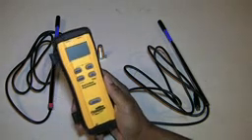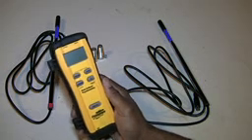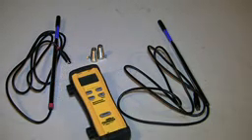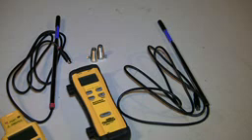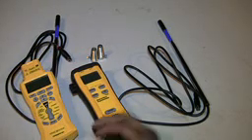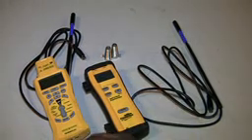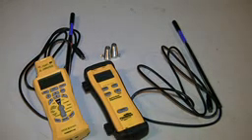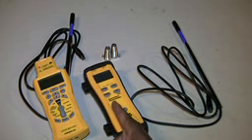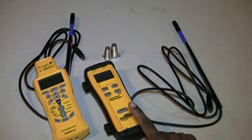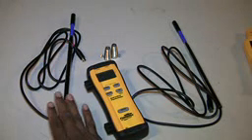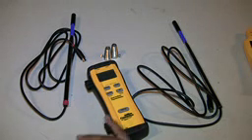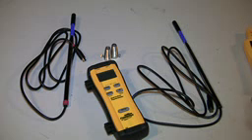The cool thing about this SDP2 is that it is a wireless device. I can sync this with my HVAC guide if I wanted to record measurements throughout a particular time. Or if I am outside with my S-Man 4 manifold and I want to record my indoor wet bulb as a return, I can sync the return probe readings with my S-Man 4, send to it the indoor wet bulb, measure the outdoor dry bulb, and then punch those numbers in my S-Man 4.